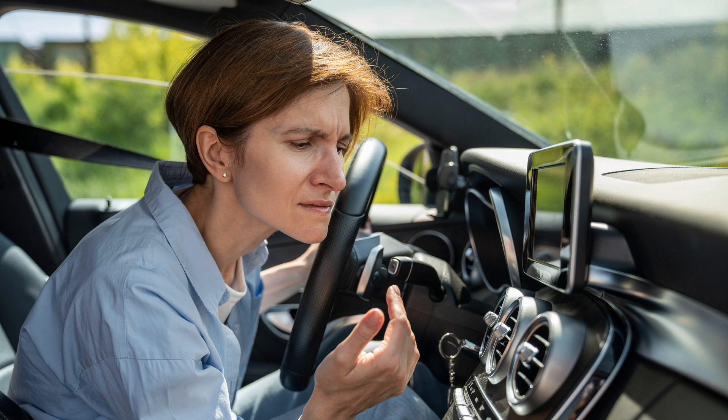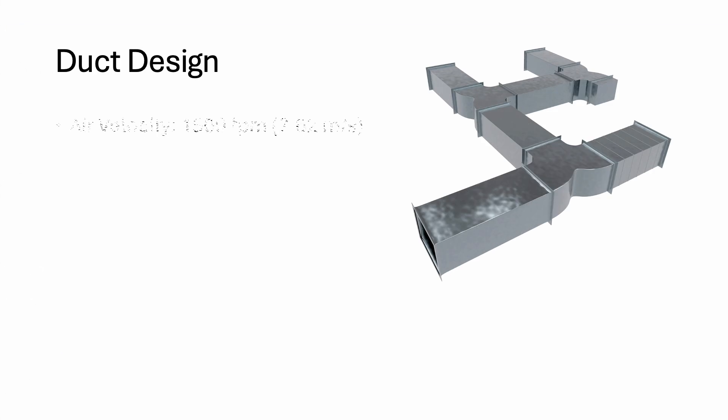What I'm trying to say here is, if the air velocity is too high, it is uncomfortable for the people sitting under the diffuser. Air conditioning ducts are typically designed at an air velocity of around 1500 feet per minute, or 7.62 meters per second. This velocity is good for the duct, but as a supply airflow, this velocity is too high.